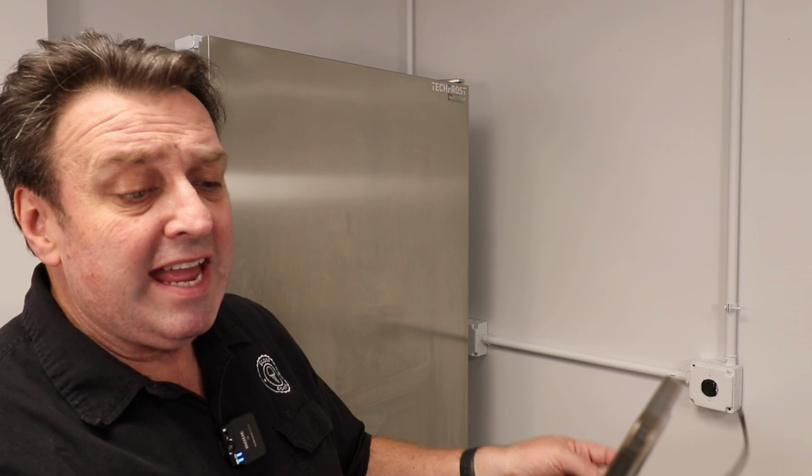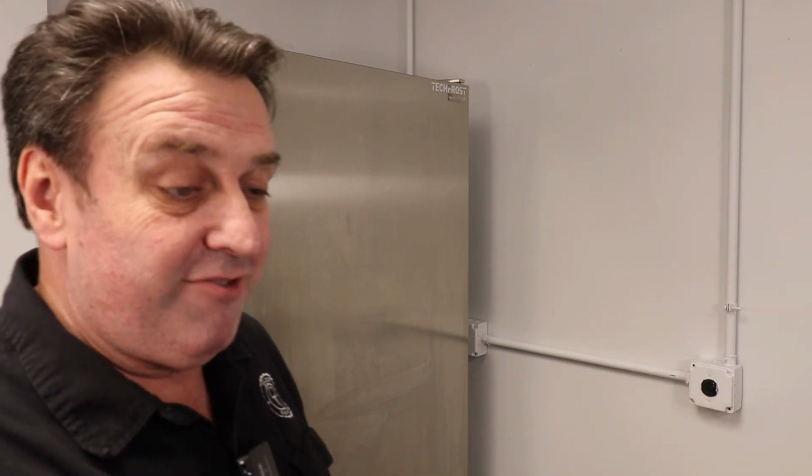Do you have a blast freezer? Is the fan for the freezer they are in on the top of the unit blowing down? Yes to both. You see that sometimes when the fans blow down from the ceiling, if the top shelf is full, the air circulation doesn't reach the bottom pints and containers, and they can collapse a little bit. So overcrowding pretty much. If we remove the product from the top shelf, it should help then? Absolutely, or at least stagger them. I guess we moved them so fast during the summer, they didn't have time to shrink, and now it's slowed down, it's becoming an issue. Thank you again for answering all my questions.